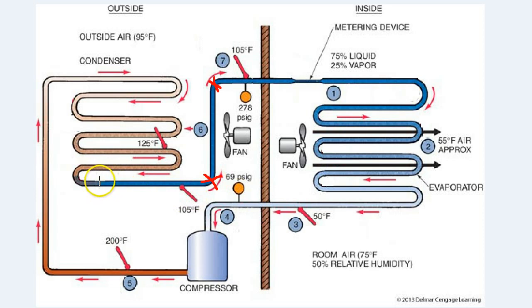If we are exactly at the saturation point, 100% liquid with no subcooling, if we hit a little kink or a bend, it will drop the pressure a little bit. And if you have enough kinks and bends or a long enough line set, the refrigerant is going to start to flash back from liquid to vapor long before it hits the metering device inside the house. So, it is really important that we have a good subcooling and a solid column of liquid to hit the metering device as it enters the evaporator coil.